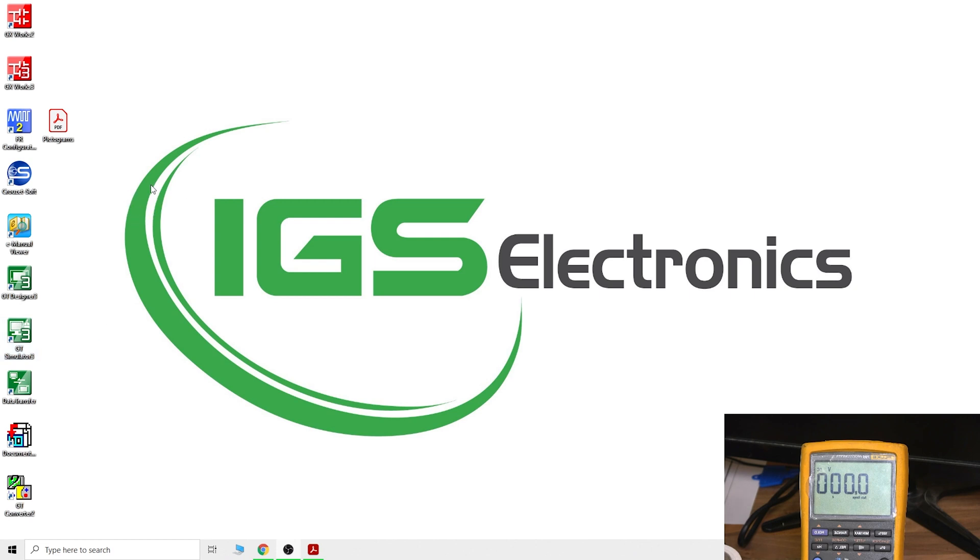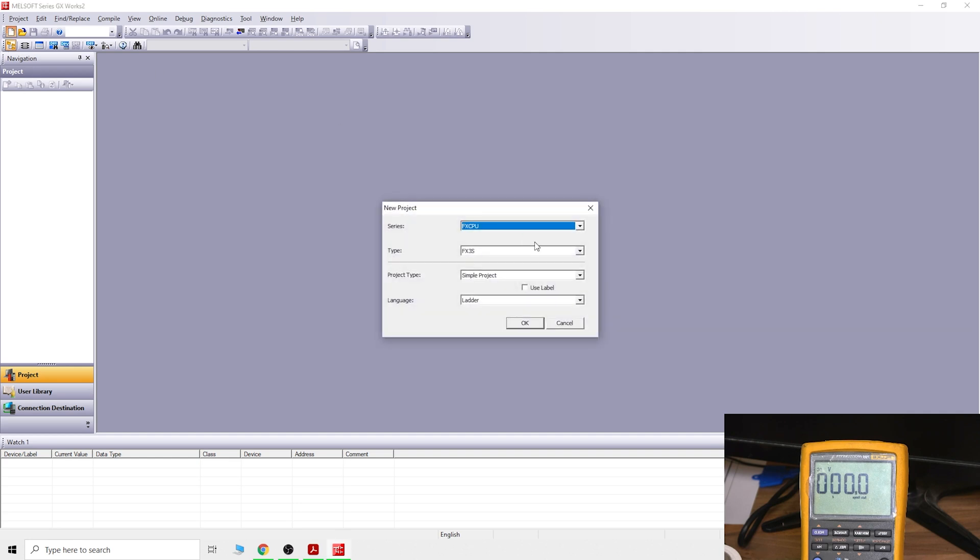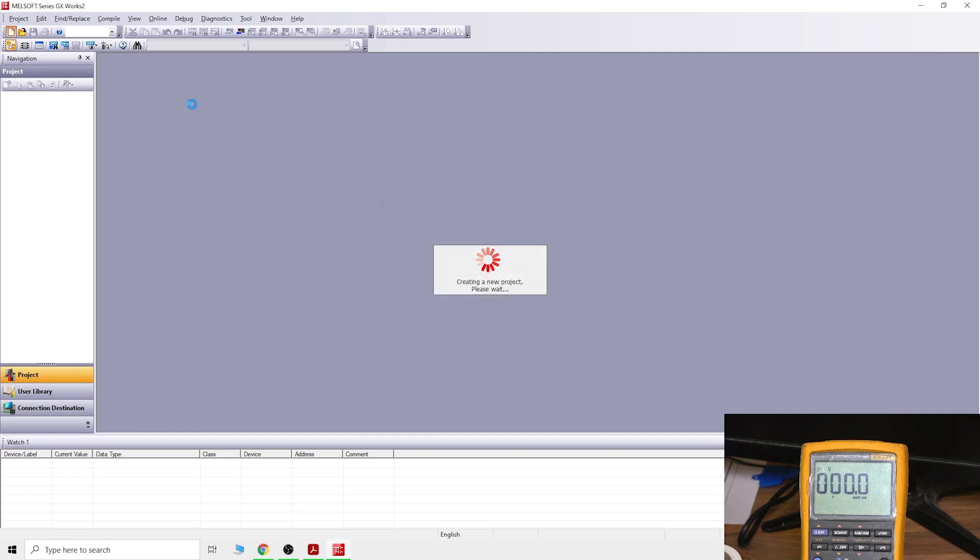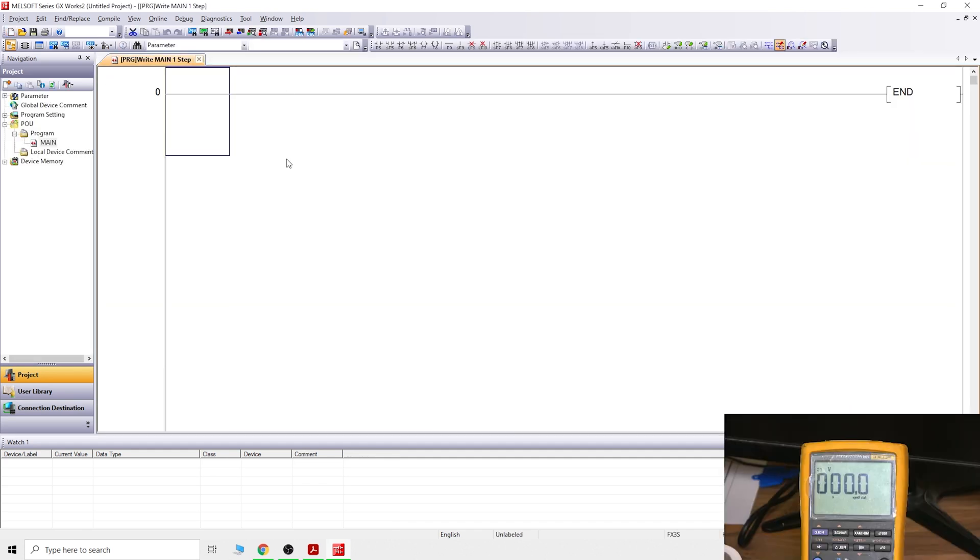Again, you can see the same data registers as for analog input card, the same ones for analog output card, but it is done differently. As you can see down there, program example, now we are sending data from D100 to D8260, so whichever channel we're using. Let's go and check it out. We've got the meter down here in the corner, which is already connected to plus and minus. GX Works, let's start it up.